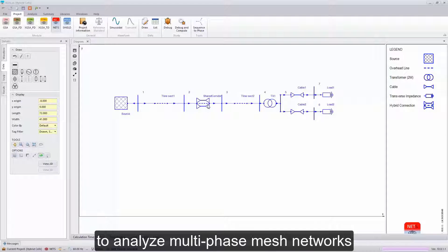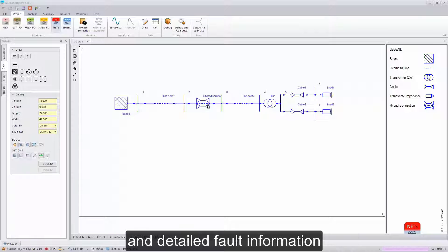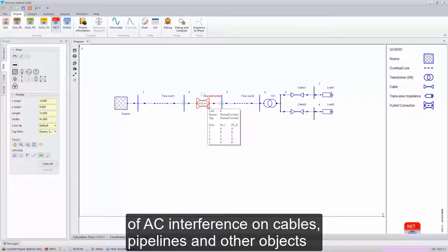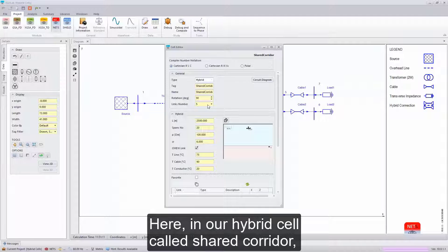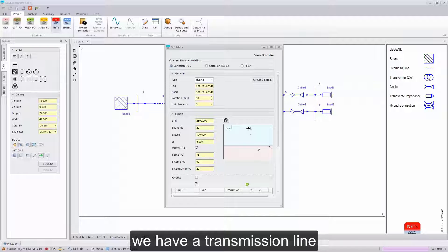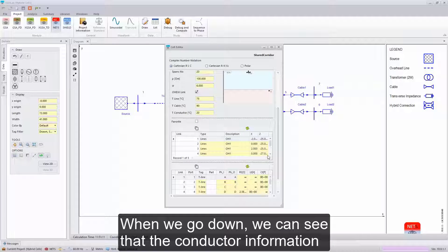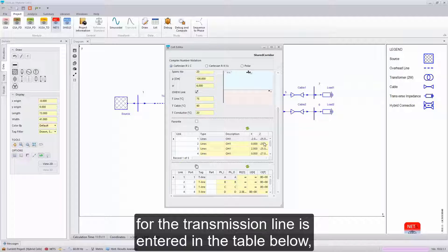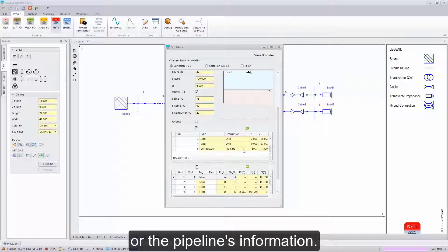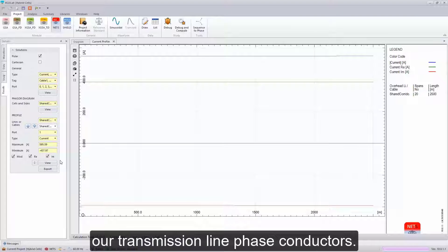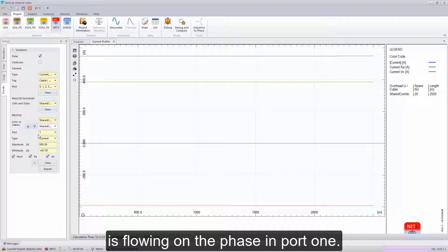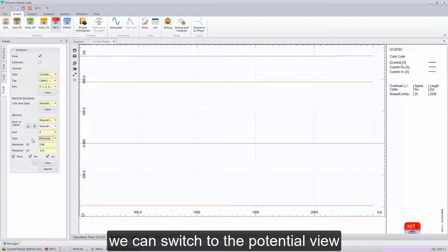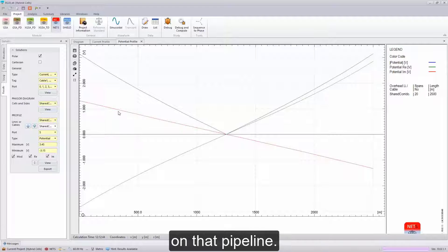The NETS module has allowed you to analyze multi-phase mesh networks for steady state, unbalanced power flow, and detailed fault information for current into the earth and alternative paths. The hybrid cell feature allows you to analyze the effects of AC interference on cables, pipelines, and other objects in shared corridors. Here, in our hybrid cell called shared corridor, we have a transmission line, and adjacent to it is a buried pipeline. When we go down, we can see that the conductor information for the transmission line is entered in the table below, as well as the conductor information or the pipeline's information. Looking at the results, we can evaluate the current that's going through our transmission line phase conductors. Here we see approximately 500 amps of steady state current is flowing on the phase in port one. When we go to port five, which represents our pipeline, we can switch to the potential view and see that approximately three volts is induced on that pipeline.